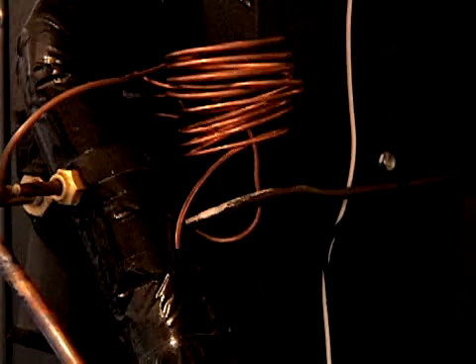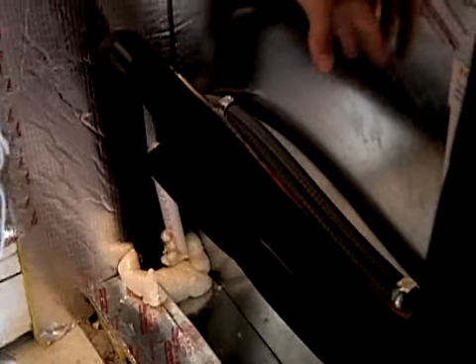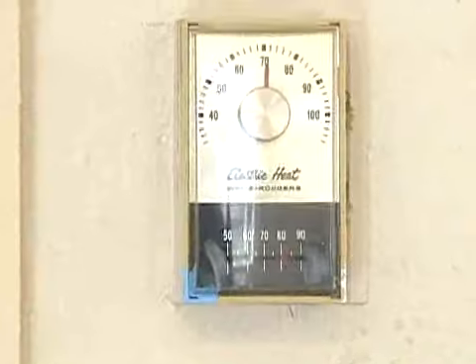Make sure you have sealed duct work, your equipment is being maintained, coils are clean, drain lines clean, proper charge, and operate at the highest possible comfortable temperature. One of the efficiency upgrades made here at the Learning Center was changing out this manual thermostat for a programmable digital one — an upgrade FPL experts say can save you instant cash.